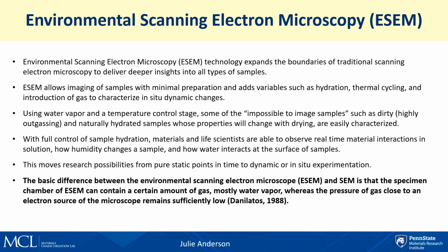The E-SEM, as it's also called, expands the boundary of the traditional scanning electron microscope to deliver deeper insights into all types of samples. E-SEM allows imaging of samples with minimal preparation and adds variables such as hydration, thermal cycling, and an introduction of gas to characterize in situ dynamic changes. Using water vapor and a temperature control stage, some of the most impossible to image samples, such as dirty, highly outgassing, naturally hydrated samples whose properties will change upon drying, are able to be imaged.